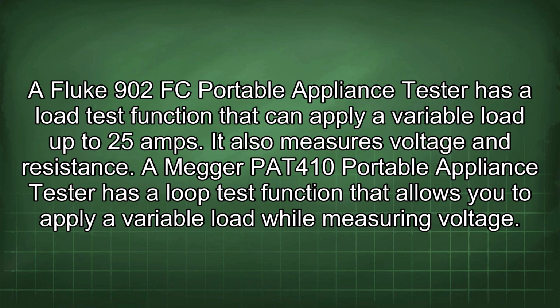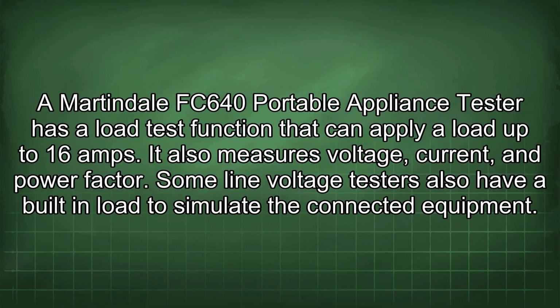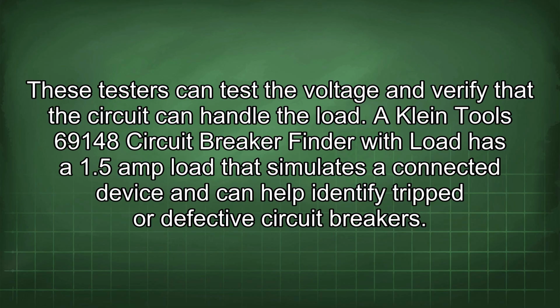A Megger PAT410 portable appliance tester has a loop test function that allows you to apply a variable load while measuring voltage. A Martindale FC640 portable appliance tester has a load test function that can apply a load up to 16 amps. It also measures voltage, current, and power factor. Some line voltage testers also have a built-in load to simulate the connected equipment. These testers can test the voltage and verify that the circuit can handle the load.